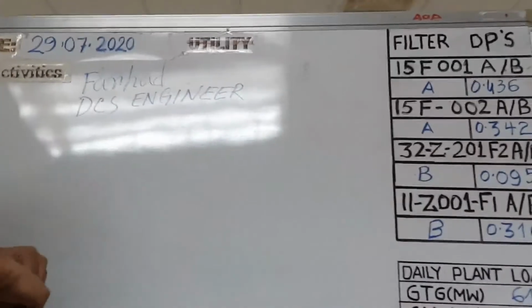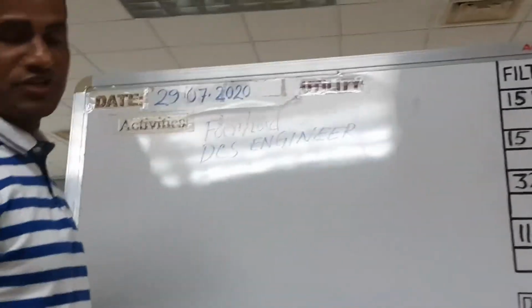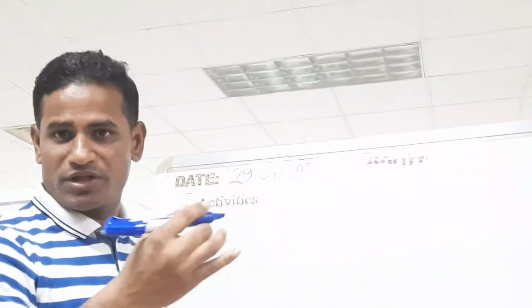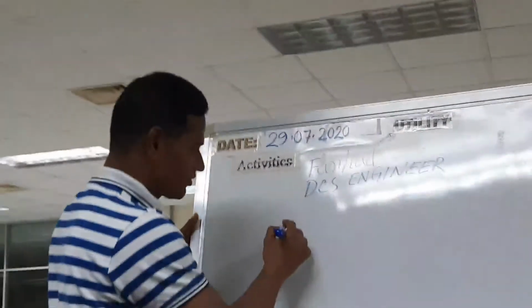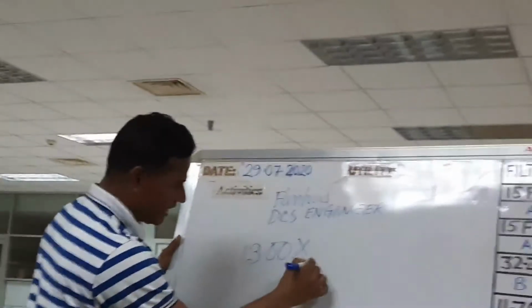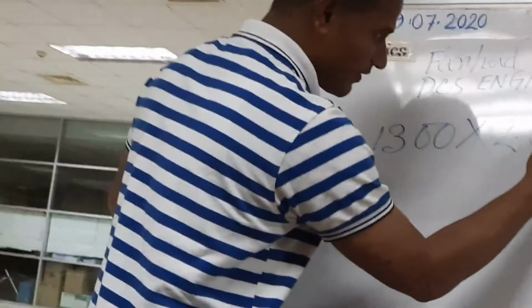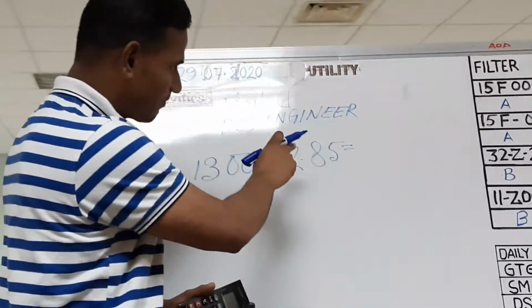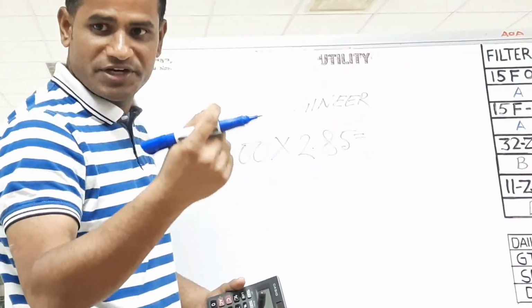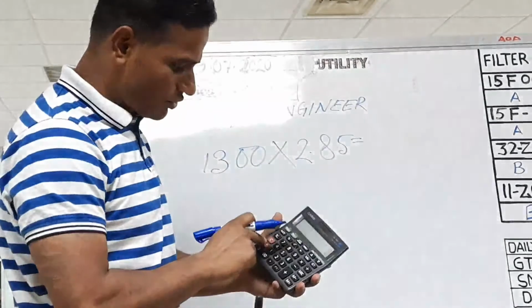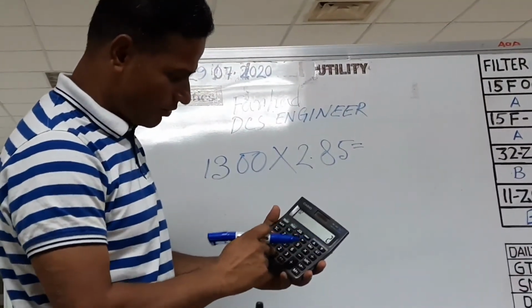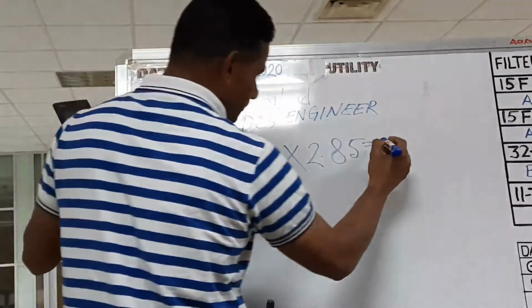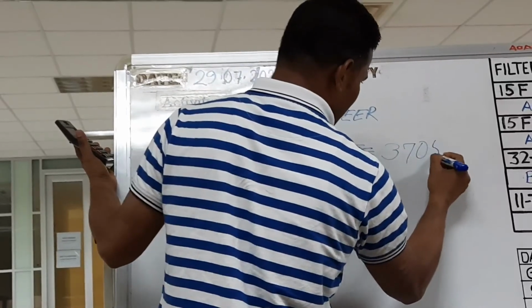Okay, Mr. Mansur. I told you our nitrogen unit capacity is 1300. For 1300, how much air flow is required? You can calculate with production 1300 and air ratio 2.85. For producing 1 normal meter cube of nitrogen, the required air is 2.85. So 1300 into 2.85 is around 3705 normal meter cube per hour.